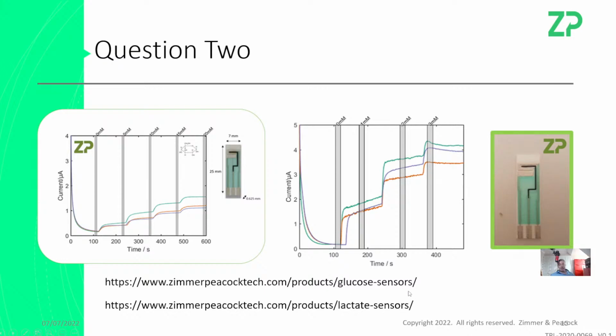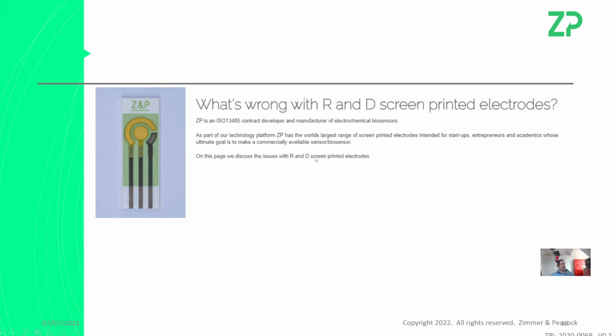These links will at least give you a reference point so that you can compare what you're doing to what we're doing. It's probably worth noting that people are sometimes worried that these smaller electrodes won't give you a strong signal. We've got strong signal here: 0 millimolar glucose and 5, 10, 15, 20. They're very clear signals, so I won't worry about signal strength too much. I know lots of people are very interested in these circular electrodes, and I have a little article online that basically talks about what's wrong with screen printed electrodes, or what's wrong with R&D screen printed electrodes.